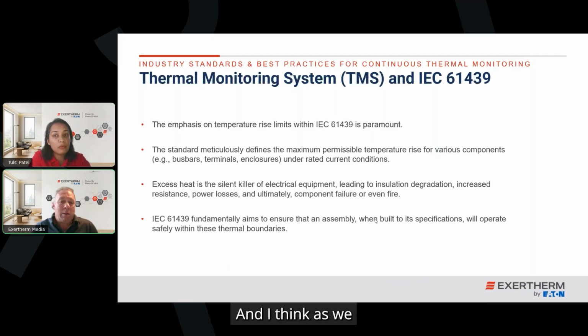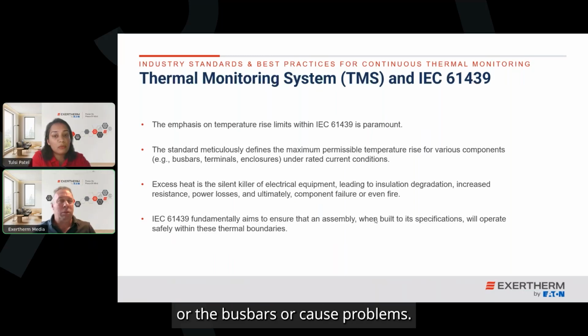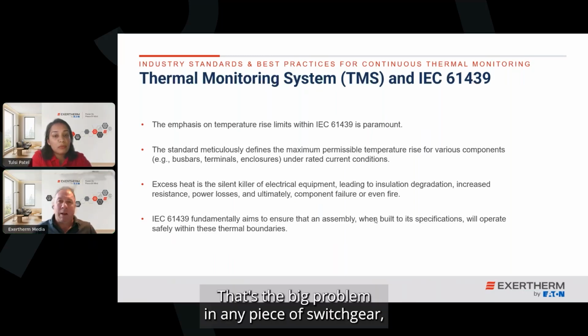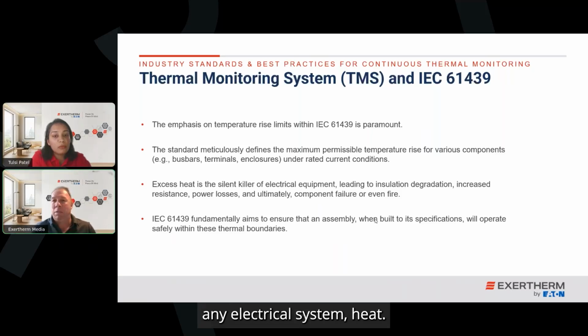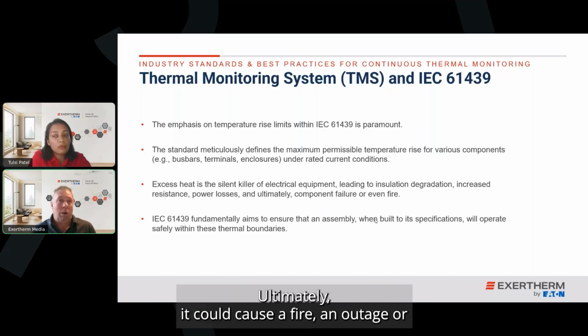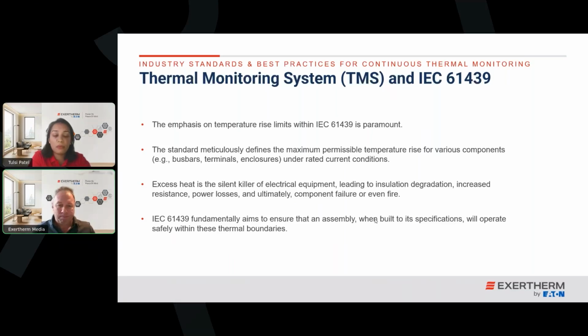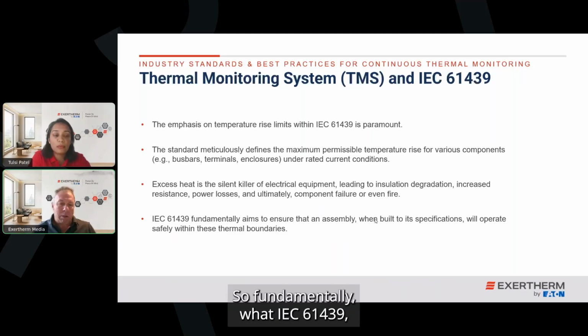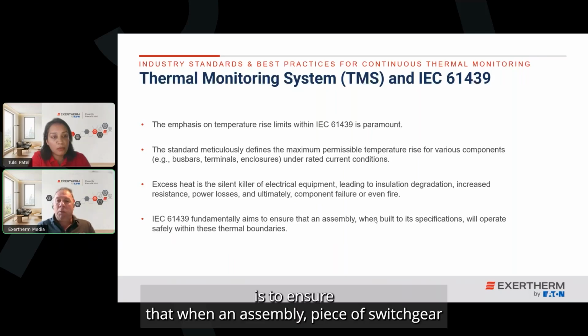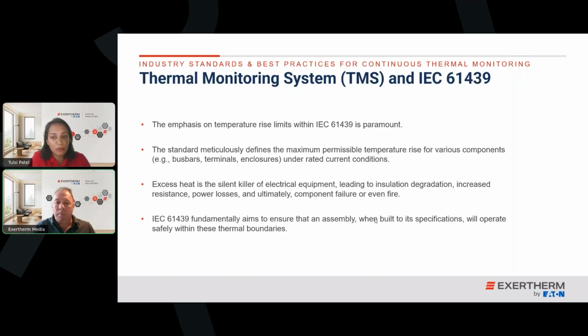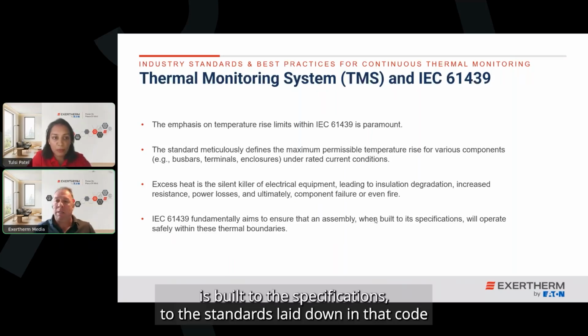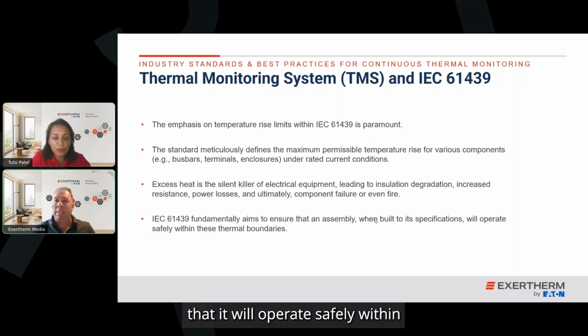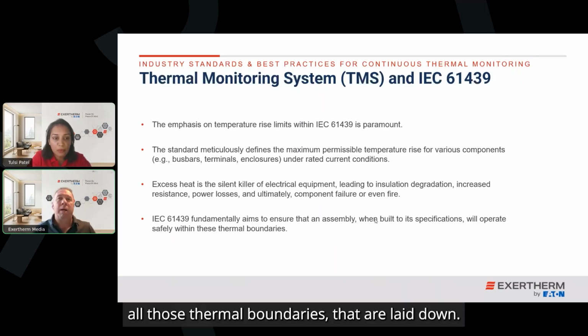And I think, as we all know, excess heat is the killer. That's what will kill either the components or the bus bars or cause problems. That's the big problem in any piece of switchgear, any electrical system: heat. Heat is not what we need. We have to get rid of that heat. And ultimately, it could cause a fire, an outage, major safety problems. So fundamentally, what IEC 61439 aims to ensure is that when an assembly, a piece of switchgear, is built to the specifications, to the standards laid down in that code, it will operate safely within all those thermal boundaries that are laid down.